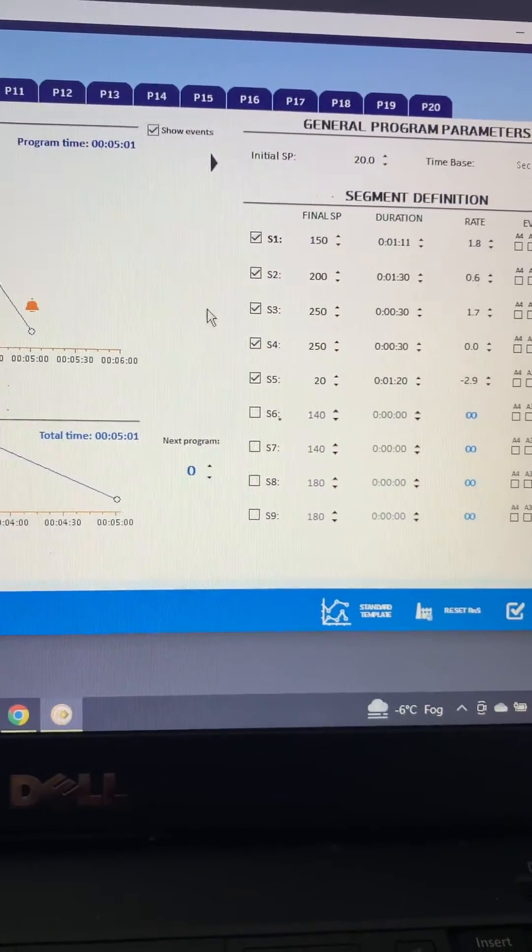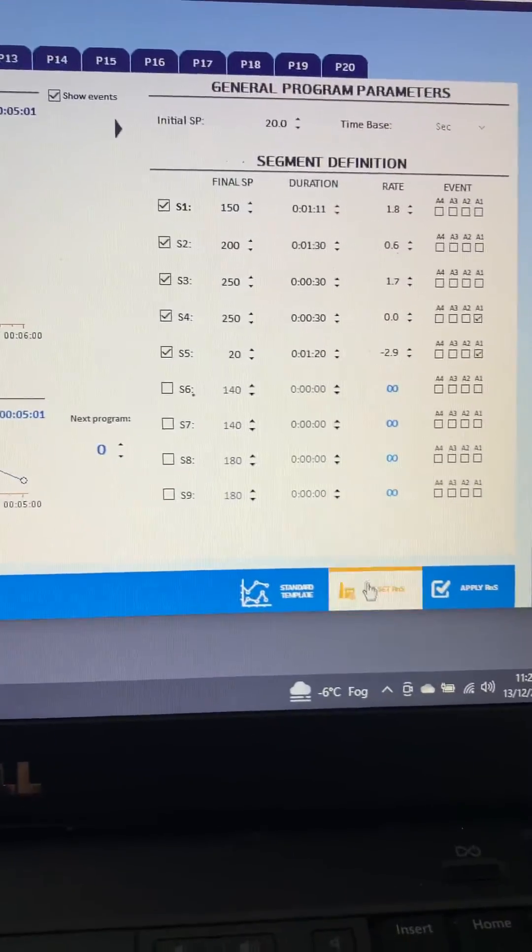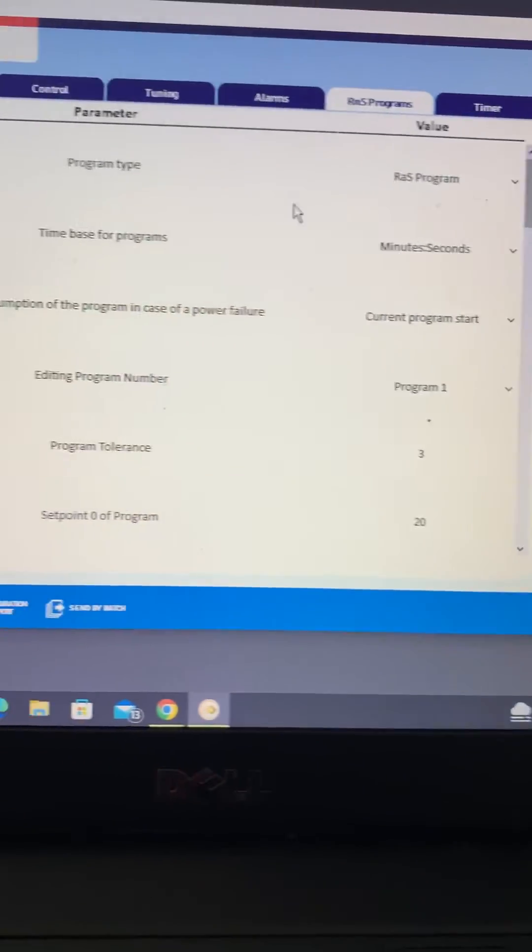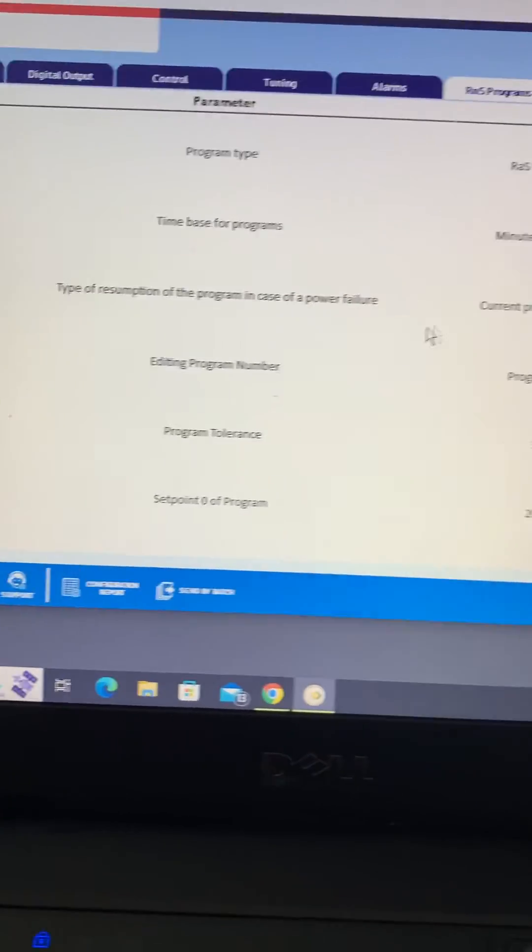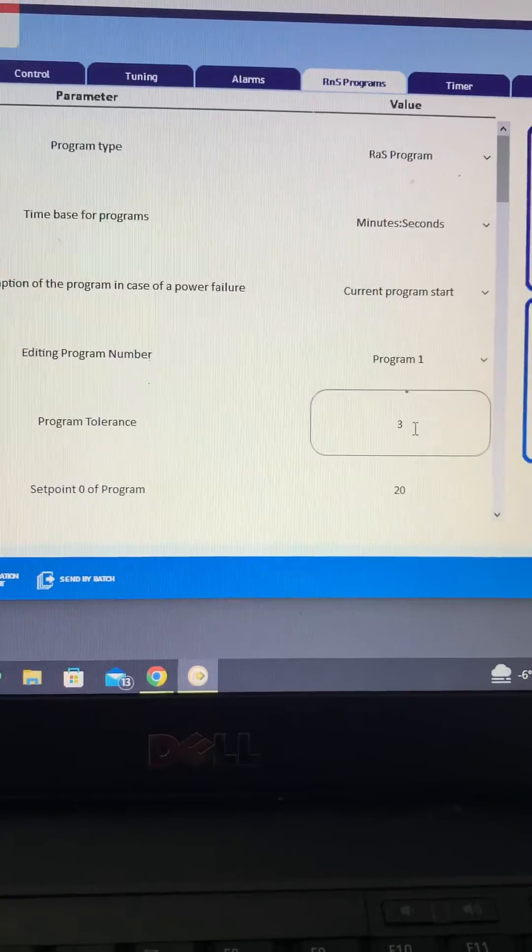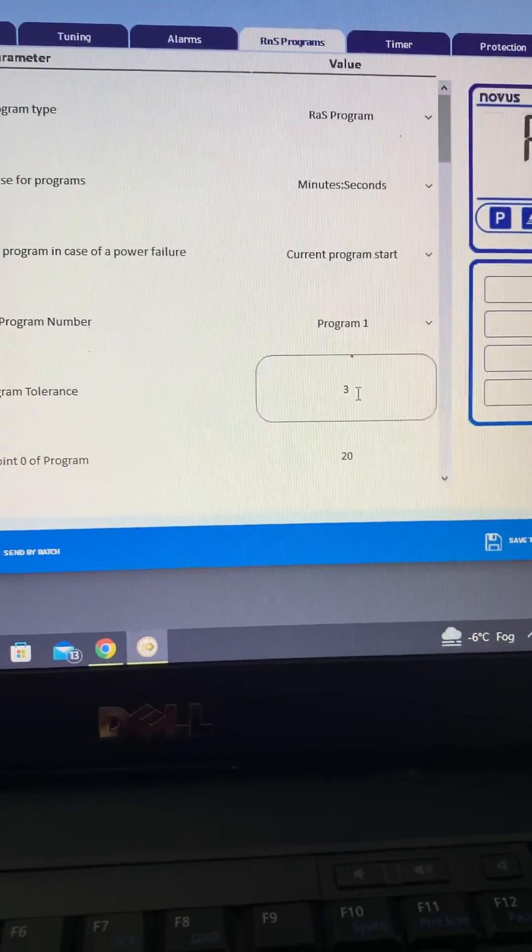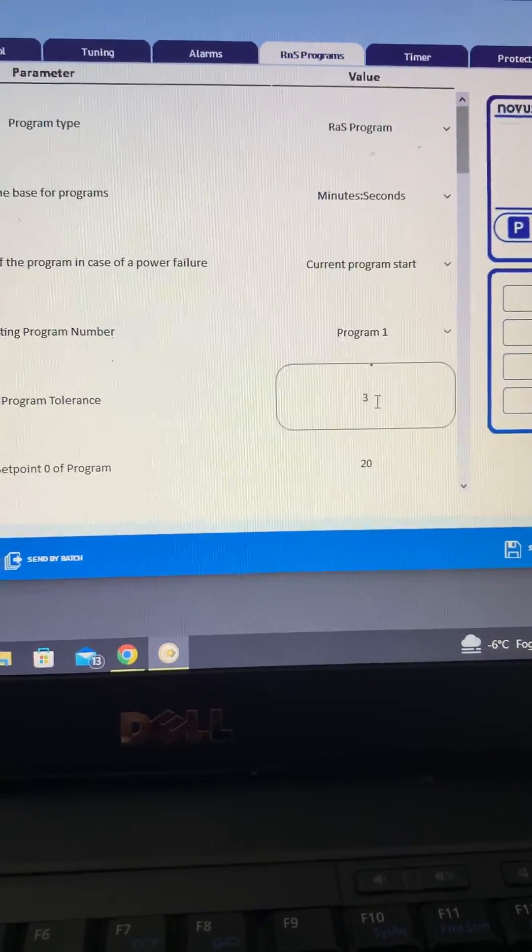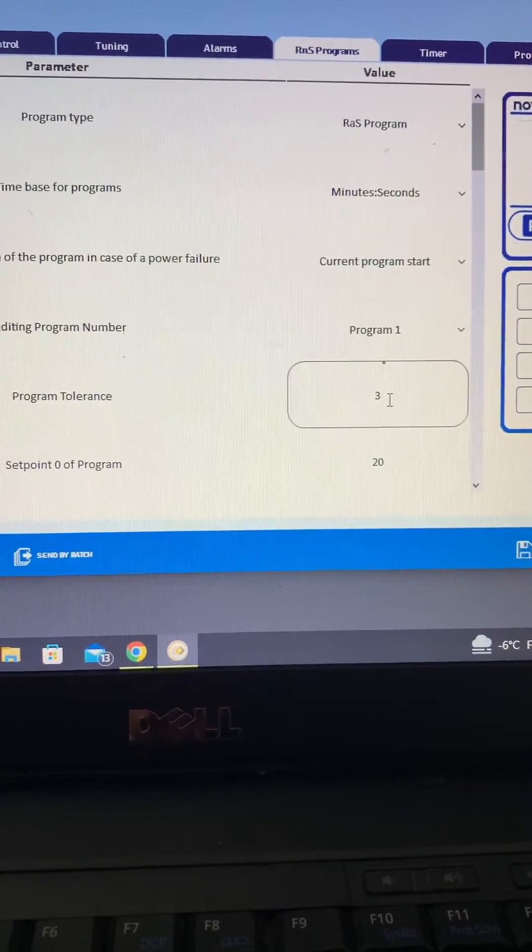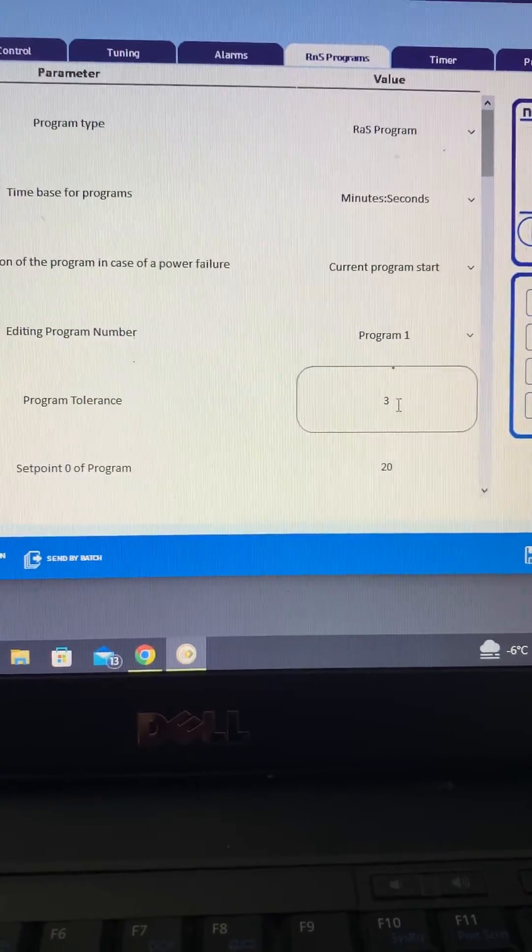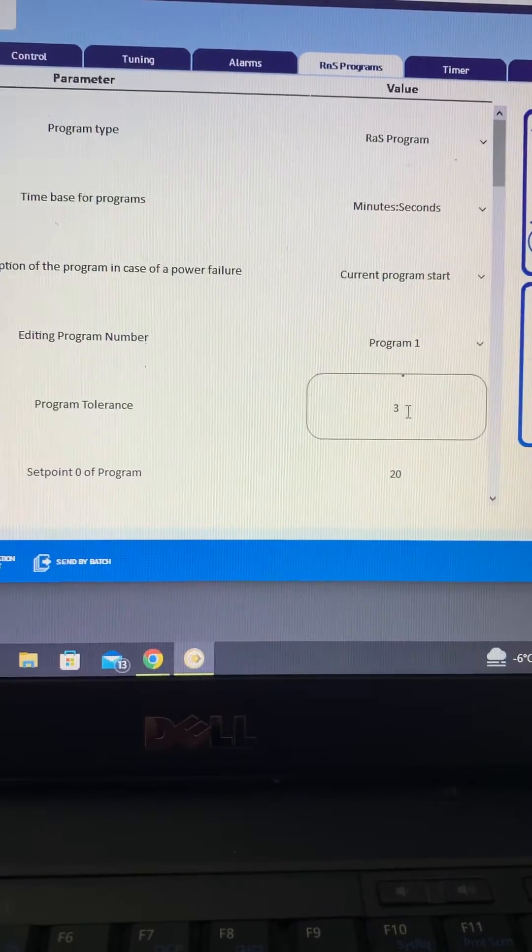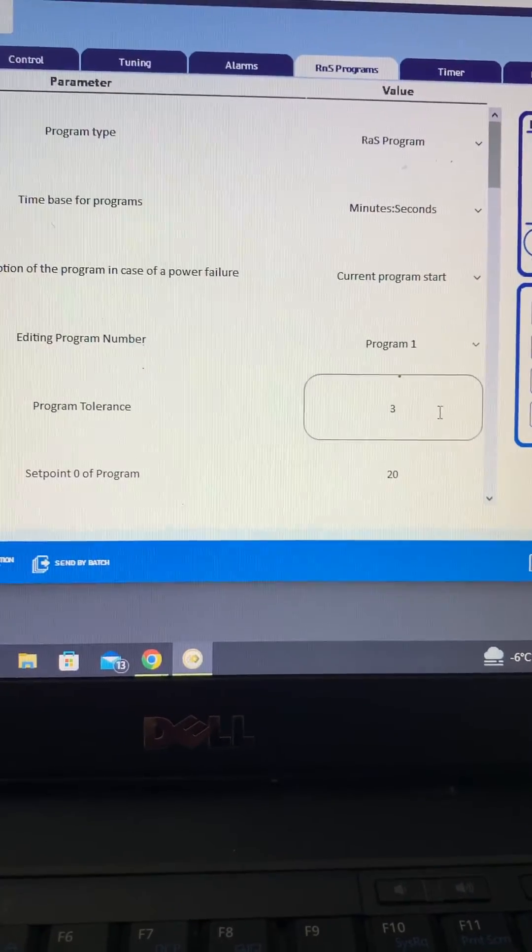So yeah, that is the basics of the ramp and soak. Now what we're going to do is just apply that and it will just write all of those values in here. Important one to point out is the tolerance, because with the tolerance of zero the program will just execute, it will just run and run. It's not looking for any temperature really to be reached as such. It's going to assume that all the temperatures are reached and just keep skipping on to the next segment. So we normally put a tolerance in of three to five degrees and then the program will actually pause and just wait for it to get back into tolerance.